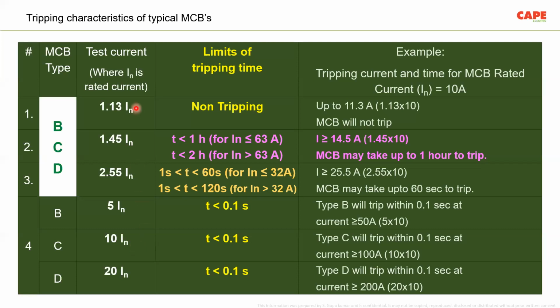So if you look at an MCB, just for your understanding, there are 3 types of MCB: B type, C type, and D type. For all of B, C, and D, when the current is 1.13 times IN, that means for a 10 amps MCB, if the current is up to 11.3 amps, this MCB need not trip. No need to trip because it is designed for that. If the current is up to 1.45 times the IN, an MCB up to 63 amps can take about 1 hour to trip. And for all OCPDs above 63 amps, it can take up to 2 hours to trip. We should always keep this in mind.